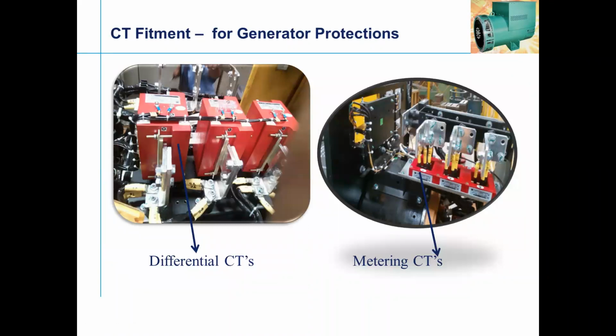Coming to the protection part which I was mentioning on the generator, the CT, the current transformer, is very important, and the capacity of the CT is very judiciously required. Most of the time, the people who buy the generator miss the protection part. We buy a generator for lakhs of investment, but protection is compromised. Presently there is a requirement from the electrical inspectorate that the CT is a must, and it should be calibrated every 2 years, and the certificate has to be submitted to the electrical inspectorate. The norms are also going to be very stringent. Maybe we can discuss the particular forms of the electrical inspectorate and the pollution control board at a later stage, during the next meeting.